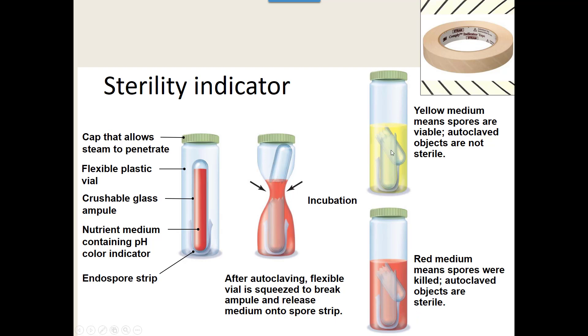We now also have indicator tape that looks like masking tape with pale white lines. At autoclave temperature for 15 minutes, these pale white lines undergo a chemical reaction and turn black. This is what the tape looks like after autoclaving. It's a lot cheaper than using all those vials.